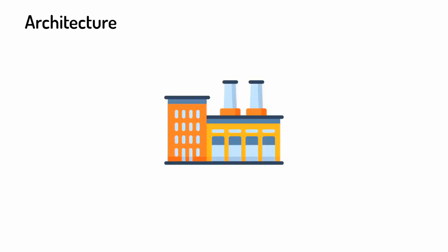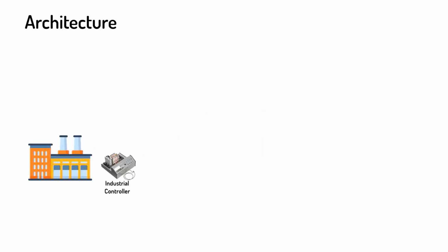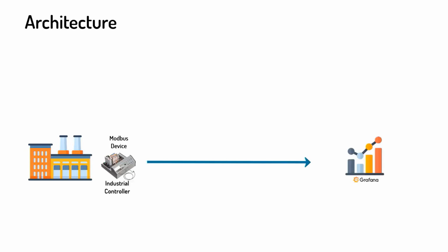So the reality is that in most factories today, the majority of production equipment still use legacy communication protocols, such as Modbus in our case. So for us to be able to collect data from this controller for real-time monitoring on the Grafana Visualisation platform, we're going to use a Schneider IIoT Gateway to act as a protocol translator, reading data via Modbus protocol on one end and converting it into an IoT protocol on the other end, which is MQTT in our case.